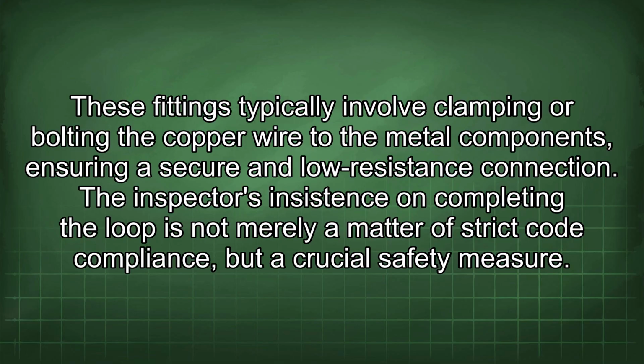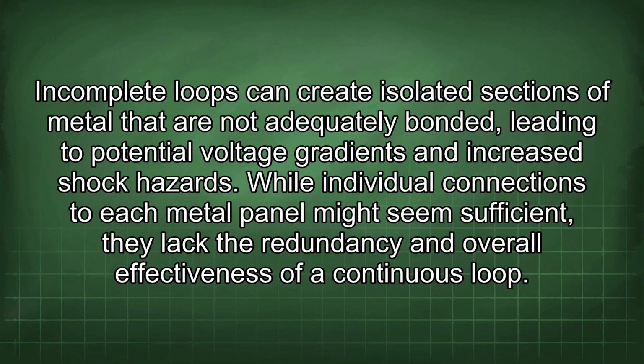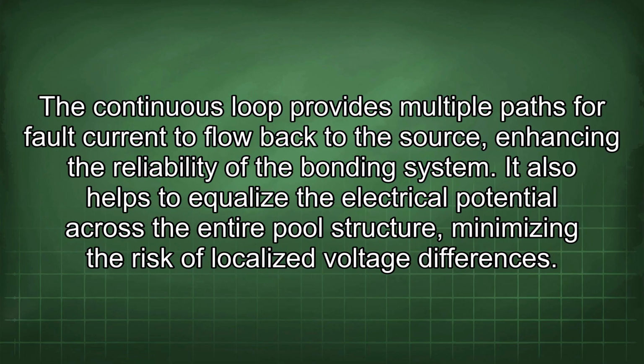The inspector's insistence on completing the loop is not merely a matter of strict code compliance, but a crucial safety measure. Incomplete loops can create isolated sections of metal that are not adequately bonded, leading to potential voltage gradients and increased shock hazards. While individual connections to each metal panel might seem sufficient, they lack the redundancy and overall effectiveness of a continuous loop. The continuous loop provides multiple paths for fault current to flow back to the source, enhancing the reliability of the bonding system. It also helps to equalize the electrical potential across the entire pool structure, minimizing the risk of localized voltage differences.